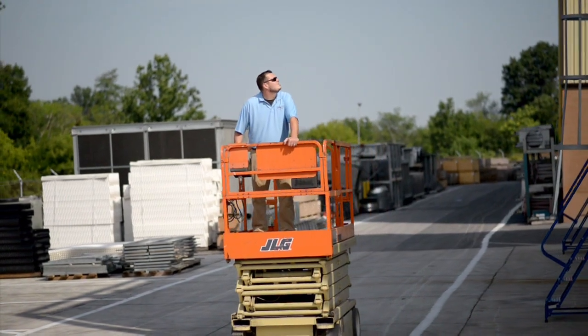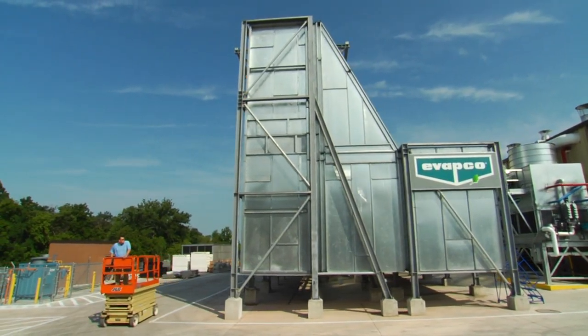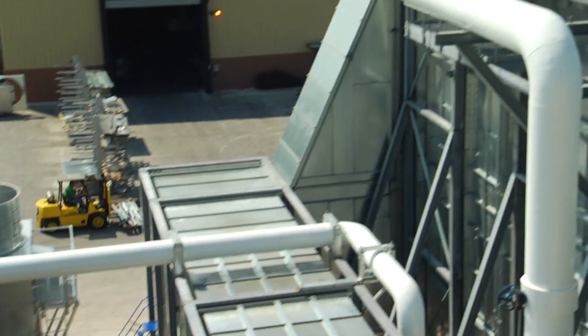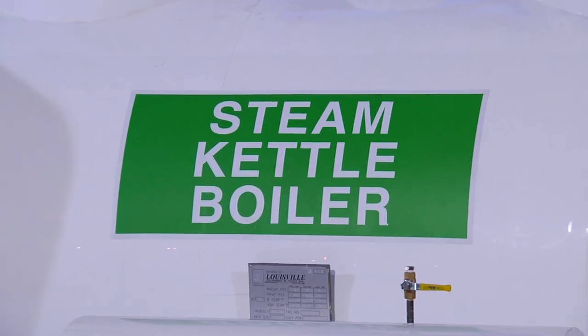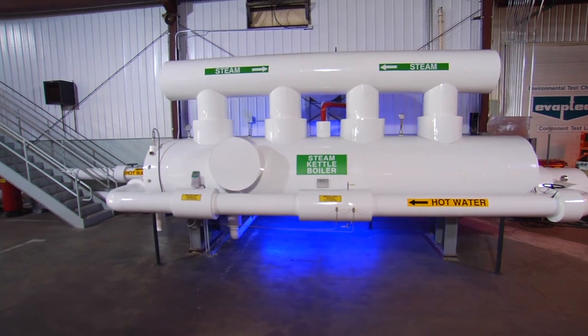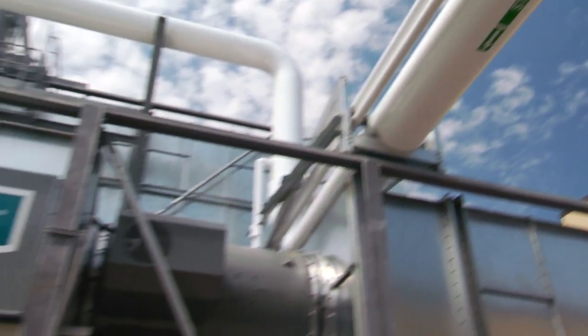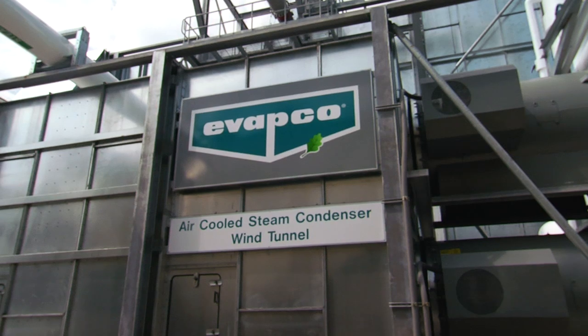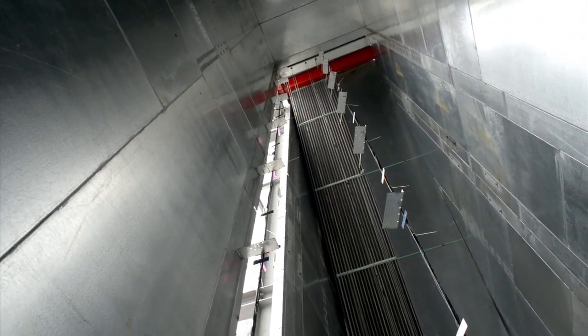This kind of heat exchanger in the past has been tested in a small scale, has been tested with water inside the tube, but that kind of testing does not describe everything that happens in terms of heat transfer. By building a test laboratory that allows us to test a full-scale, full-size heat exchanger in the same conditions as in a power plant, they condense steam at a relatively low temperature, relatively low pressure under vacuum. And being able to test the heat exchanger with steam under vacuum is unique.